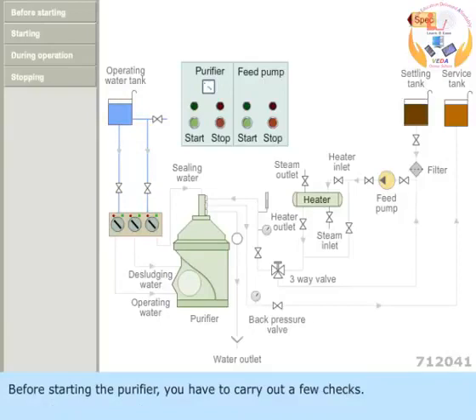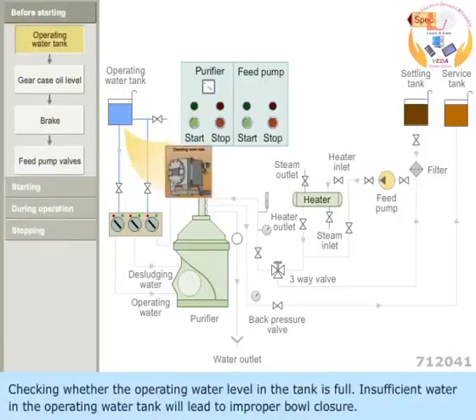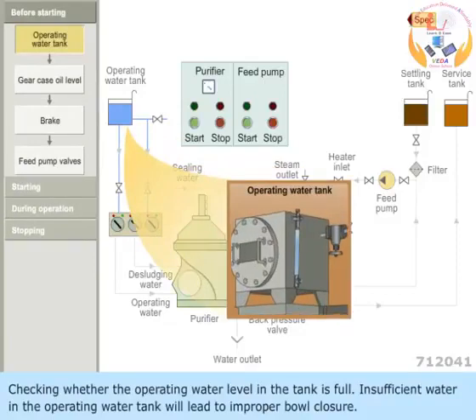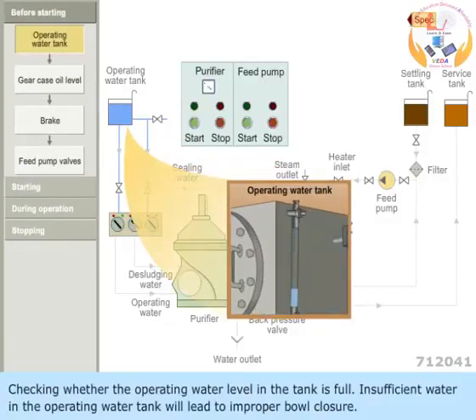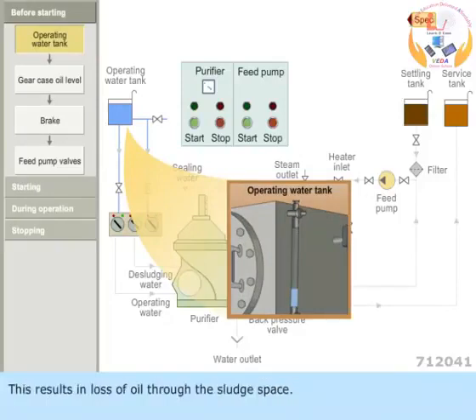Before starting the purifier, you have to carry out a few checks. Check whether the operating water level in the tank is full. Insufficient water in the operating water tank will lead to improper bowl closure. This results in loss of oil to the sludge space.